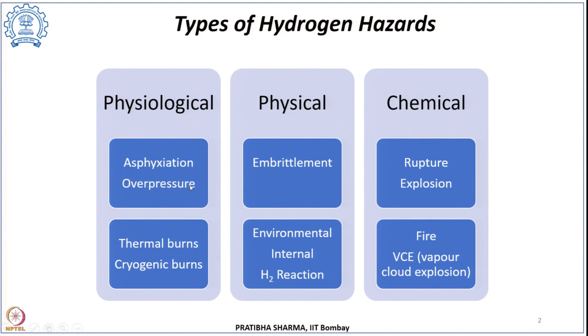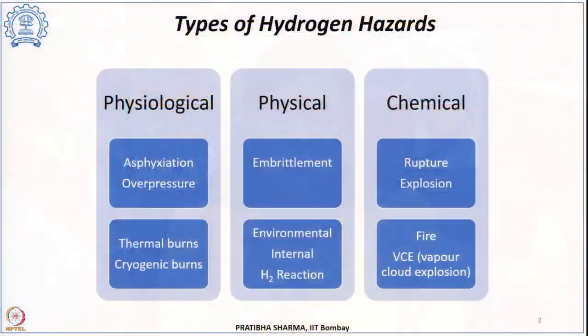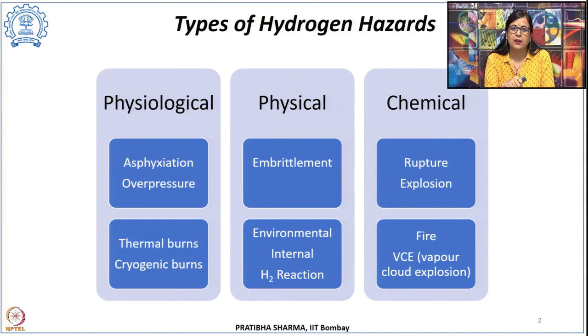The blast waves which come because of explosions — resulting from over-pressurizations — and the duration of exposure can result in several different types of injuries or organ failures. Thermal burns, which are because of the heat released and the emitted heat radiations from a fire due to a hydrogen accident, can lead to injuries to the person, damage to property, and many other losses. These thermal burns depend upon several parameters like how long the exposure has been, what was the burning rate, what was the environmental temperature and pressure, and what was the burning surface area.